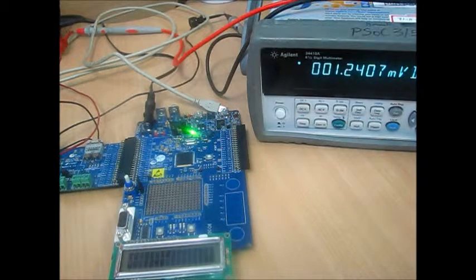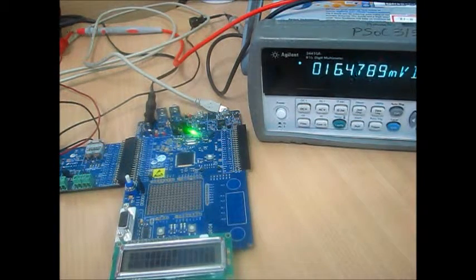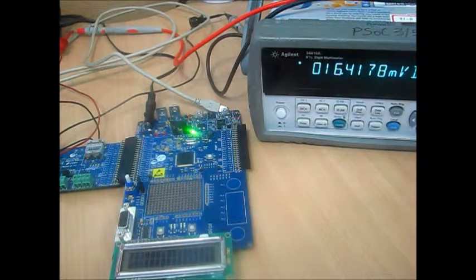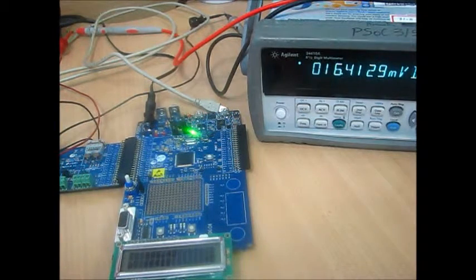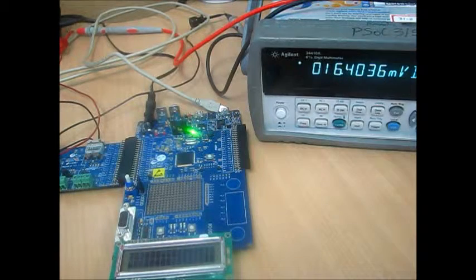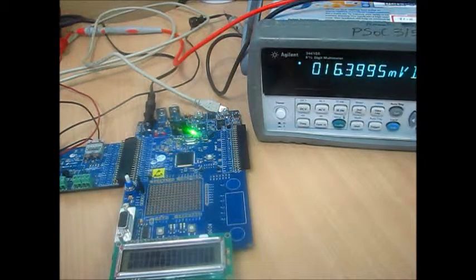Now I increase it further to somewhere close to 16 millivolts. The reading closely follows again. The potentiometer reading takes a while to settle down. It actually decreases continuously because the potentiometer is not very stable in a fixed point. You can see that the value has stabilized a bit, and both the values are approximately the same. The maximum difference is 4 microvolts.